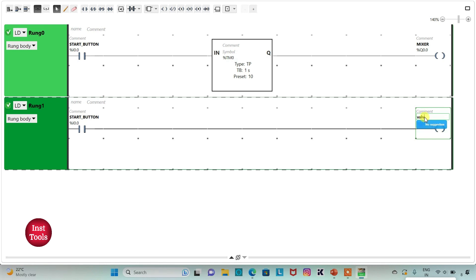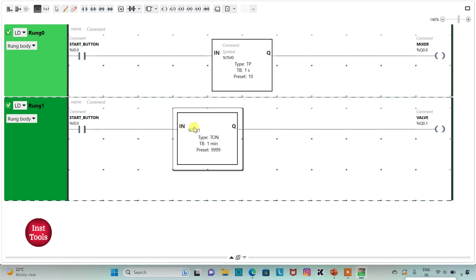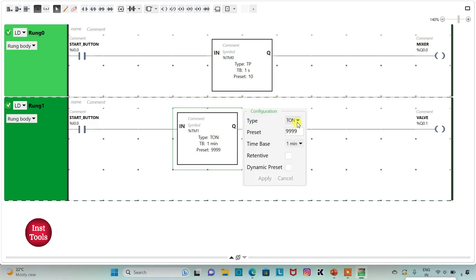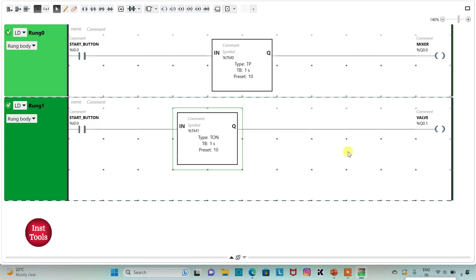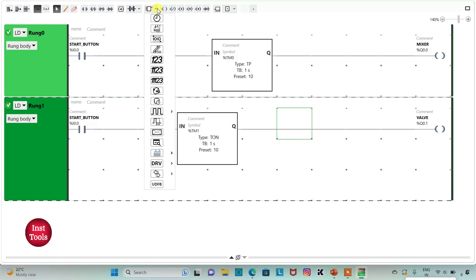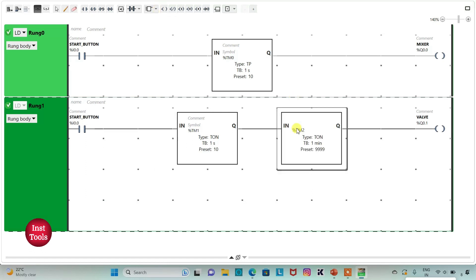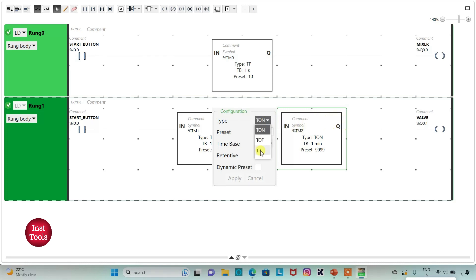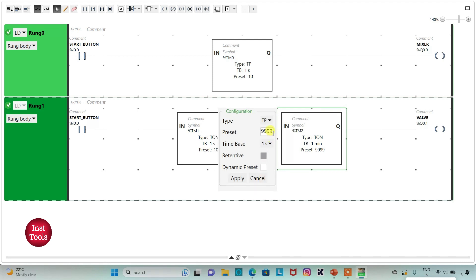Since the valve should turn on after 10 seconds, I insert a functional block timer of type TON, set time base to 1 second and preset value to 10, then click Apply. I then insert one more functional block timer of type TP, set time base to 1 second and preset value to 5, so the valve will be open for 5 seconds.